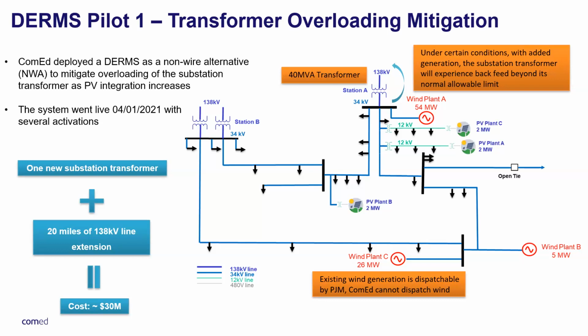That's when our Smart Grid team saw a great opportunity to demonstrate the DERMS pilot, because the real use case is to communicate with PV customers—deploying the DERMS system to talk to the PV inverters. If there's a scenario where PV output could push the transformer's reverse power flow above the threshold, we would cut off or shed those PV systems from the grid. So this is the fundamental use case.